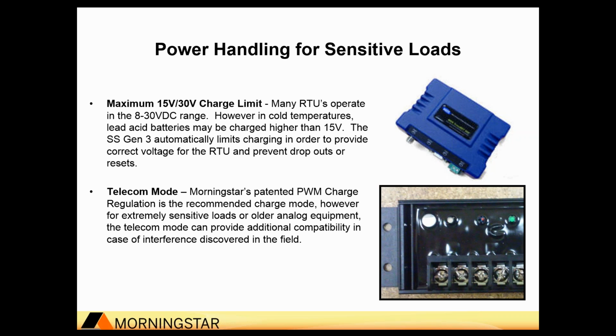And one other mention of the telecom mode, this is a little hard to see, but if you look just to the left of the green charge status LED, to the right of the temperature sensor, you'll see this small little wire loop. If you do have noise in the system, you can cut that wire loop and change the switching frequency of the controller so that it doesn't interfere with telecom loads or other sensitive loads. This is definitely a last resort. I'd always recommend going through a troubleshooting list that we have and can send to you before you go to that extent, but it's there if you need it.